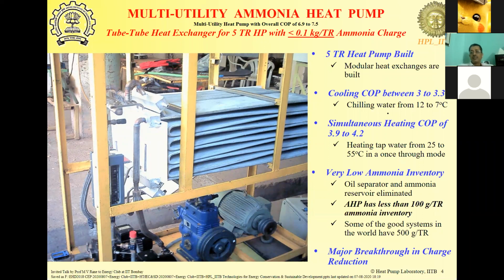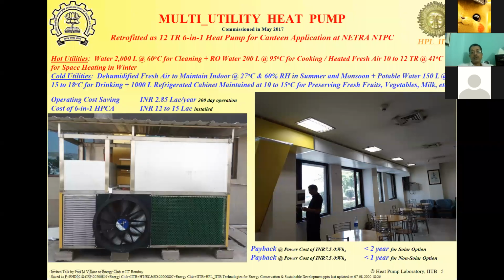Now, in this particular case, it was heating on one side as well as cooling on the other side. So it was concurrently heating water from 25 to 55 degrees centigrade here, and cooling water from 12 to 7 degrees, both happening concurrently. In this case, we needed to store the hot water or the chilled water if we did not have concurrent utility. To overcome this, we have come up with a new generation of heat exchangers, wherein this particular heat pump is one of our latest versions. This is a 6-in-1 heat pump. I described to you a 3-in-1 heat pump, which could do air conditioning, water heating or solution heating, and water cooling. This does 6 utilities concurrently.